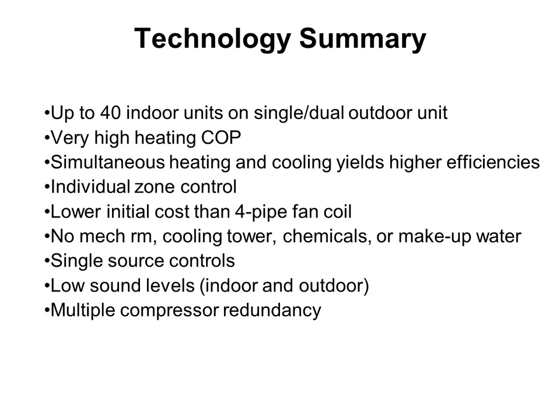I can have individual zone control just like I do with the VAV system, and arguably perhaps even smaller zones in some cases. But I can have individual zone control, so each one of my tenants or offices or whatever can have their own thermostat and get the heating and cooling that they want. Typically, install costs are lower than the 4-pipe fan coil system, and typically they're higher than a rooftop system.